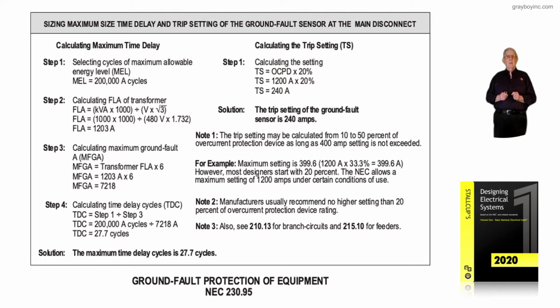disconnect. Now, step 1, we're using the maximum time delay. We're using the MEL, which is your available energy level. We're using a 200,000 amp cycle for this good rule of thumb method. Step 2, the FLA: we take the kVA of the transformer times 1,000, divide it by the voltage times the square root of 3 if it's 3-phase. Now, doing this in the illustration, we know it's 480 volt, 277, so we're going to have a 1,000 kVA transformer times 1,000 divided by 480 times the square root of 3. We come up with 1,203 amp. Now we're ready for step 3.